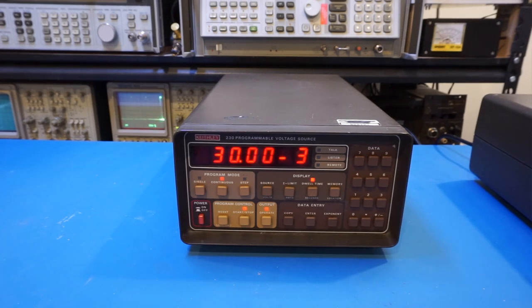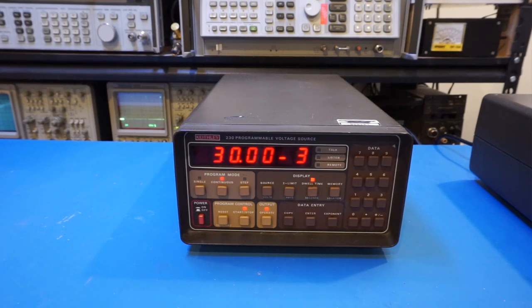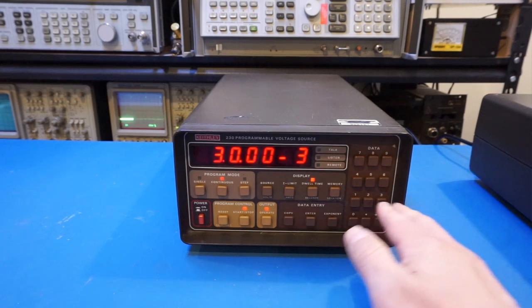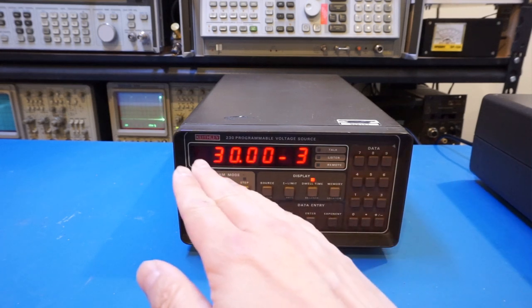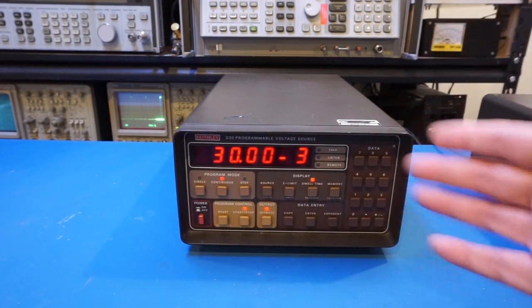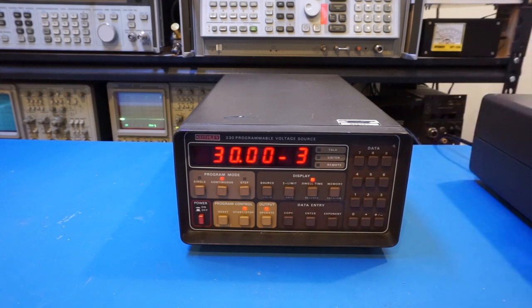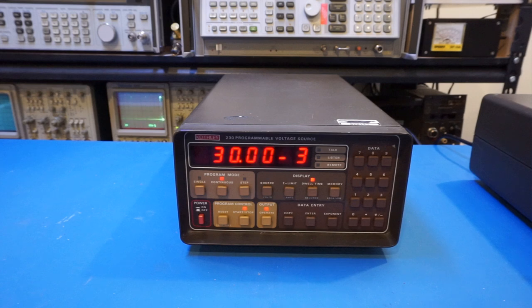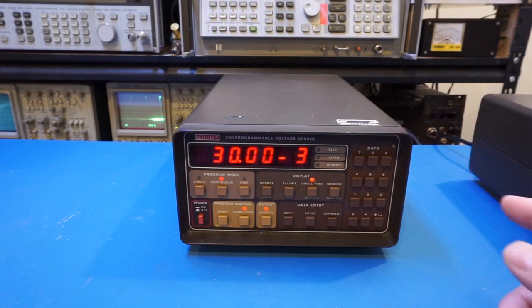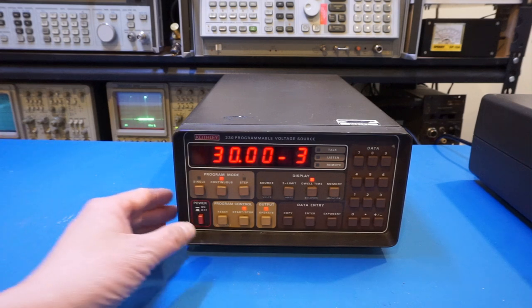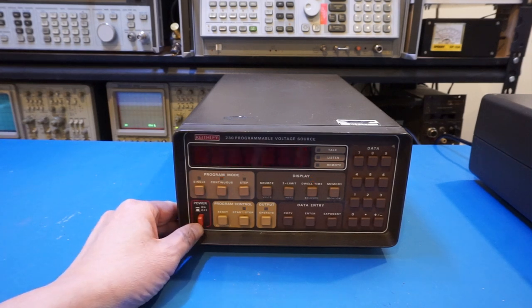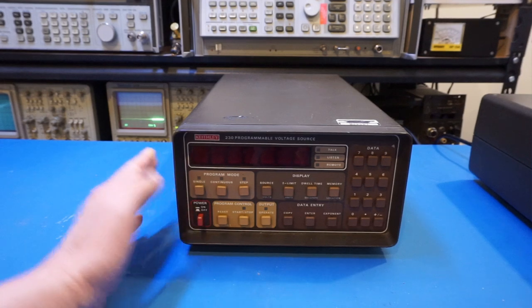So that's very easy. And of course, we can build much more complex waveforms using this instrument here. So the next thing I'm going to build is basically a staircase. And now for that, we just are going to utilize more channels. Basically, the plan is for the first channel, let's say we program zero. And second channel, we program as one volt. And then two volts, three volts, four volts, so on and so forth. Then we can form a staircase. So let's do that. And by the way, for that, I'm actually just going to clear the settings. And the easiest way to do that is just to power it off and power it back on again. Unfortunately, the Keithley 230 does not have any memory backup. So when it is powered off, everything is erased.